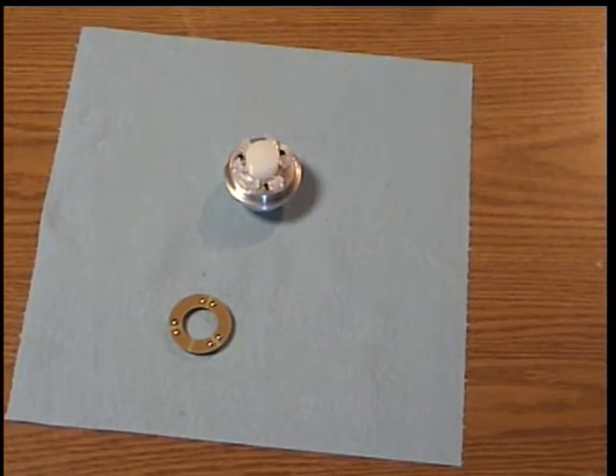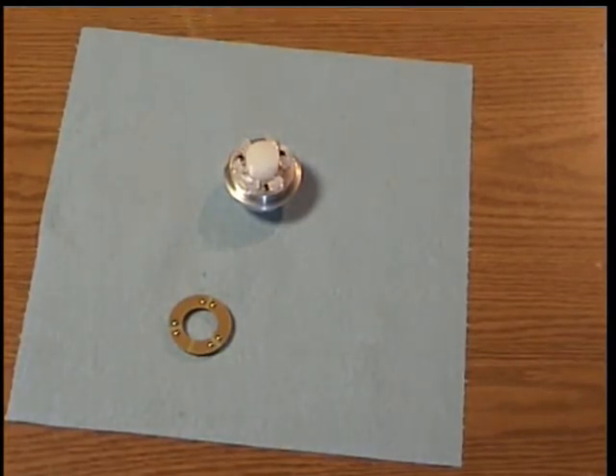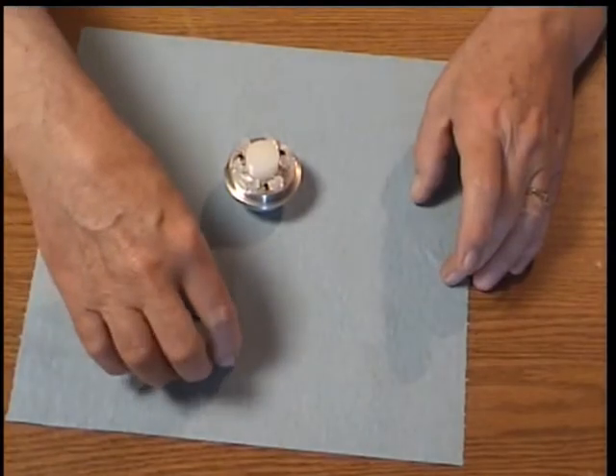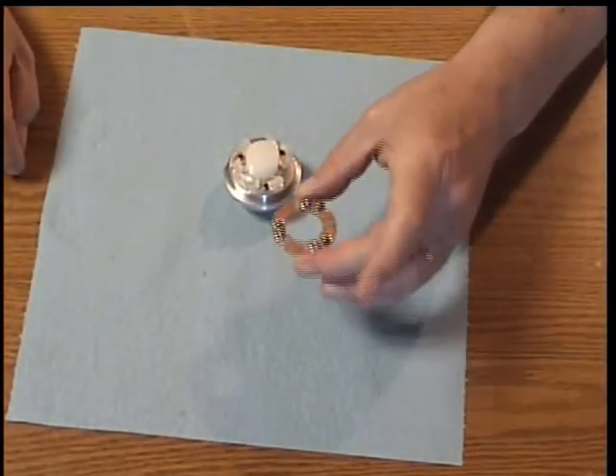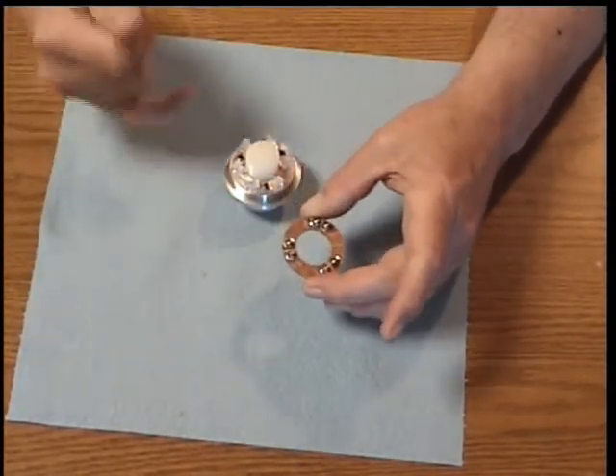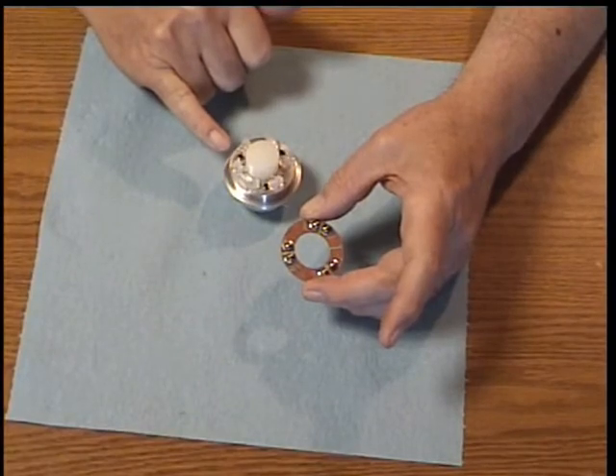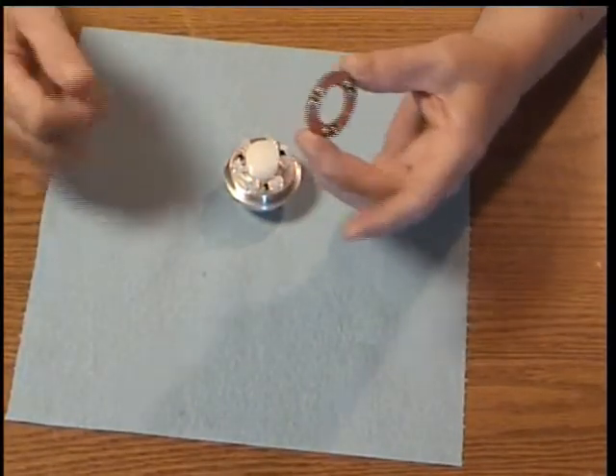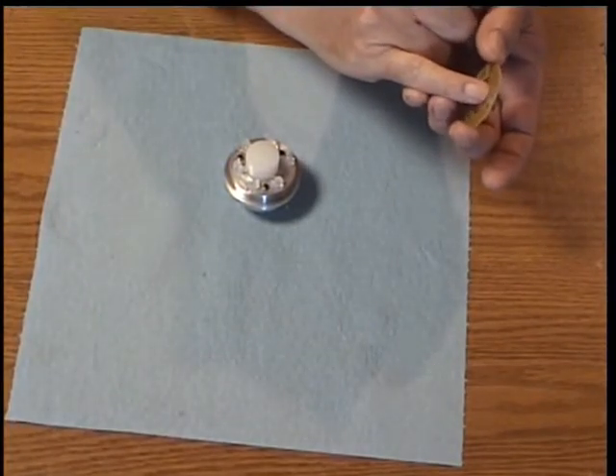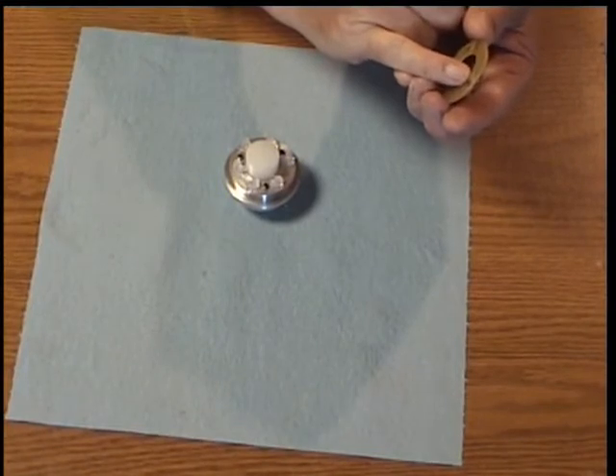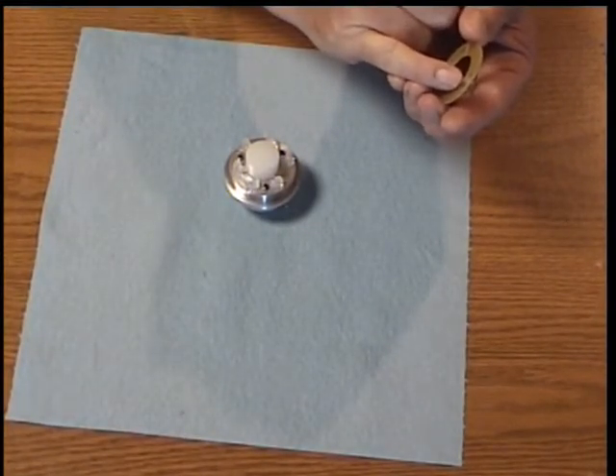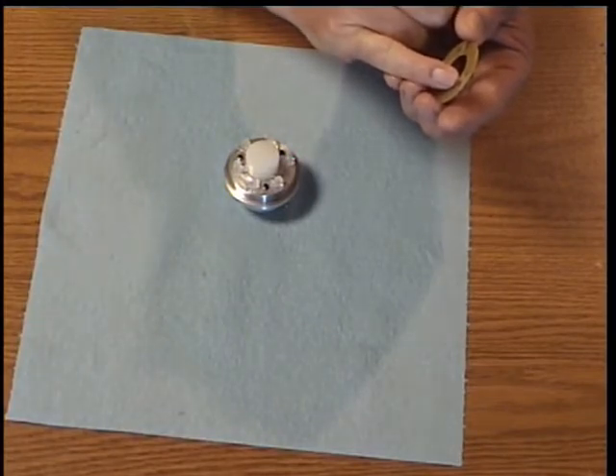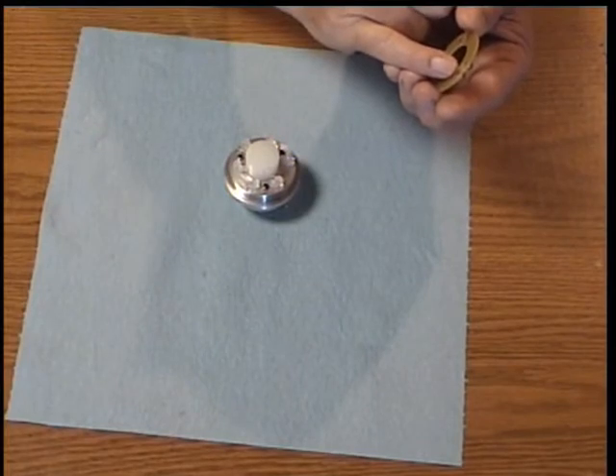Take a second here to cap up my adhesive so that it doesn't dry out. Okay, then we take the printed circuit board, the balls up, and what we want to do is place the set screw underneath the groove between the balls. Now, we need to be careful because there are openings here where the balls have been soldered in, so we want the set screw to go between these openings. We do not want to let the set screw slip down into one of these openings where it would make contact with the ball. That would make the probe totally unusable.